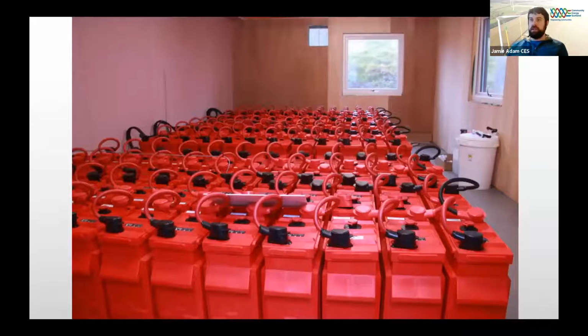And this is our batteries. They had to be in a separate room because these are vented lead acid batteries, so when they're charging they can release some hydrogen, so that has to be in a separate room to all the electrical equipment. And you have to think carefully about ventilation as well to allow any hydrogen to dissipate safely.